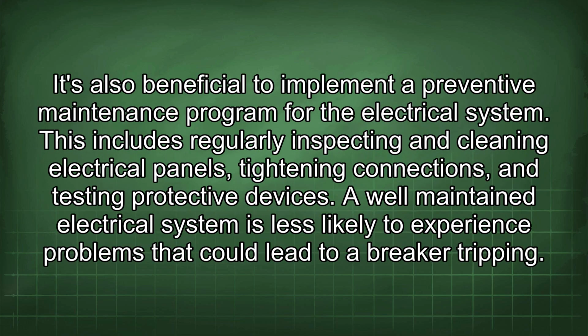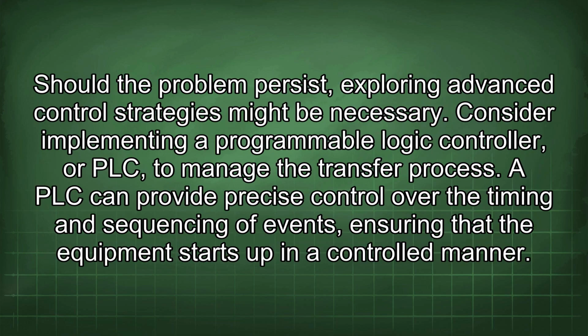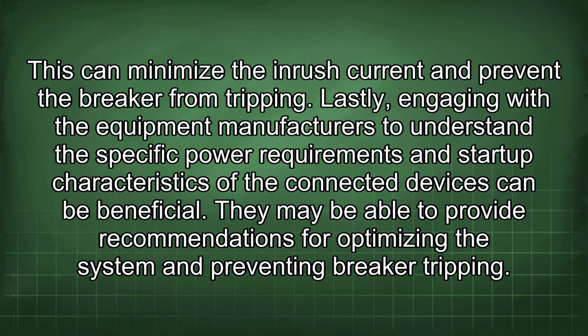It's also beneficial to implement a preventive maintenance program for the electrical system. This includes regularly inspecting and cleaning electrical panels, tightening connections, and testing protective devices. A well-maintained electrical system is less likely to experience problems that could lead to a breaker tripping. Should the problem persist, exploring advanced control strategies might be necessary. Consider implementing a programmable logic controller, or PLC, to manage the transfer process. A PLC can provide precise control over the timing and sequencing of events, ensuring that the equipment starts up in a controlled manner. This can minimize the inrush current and prevent the breaker from tripping.